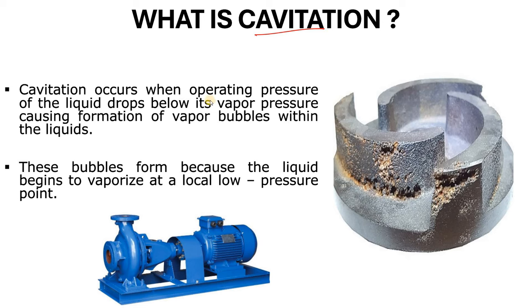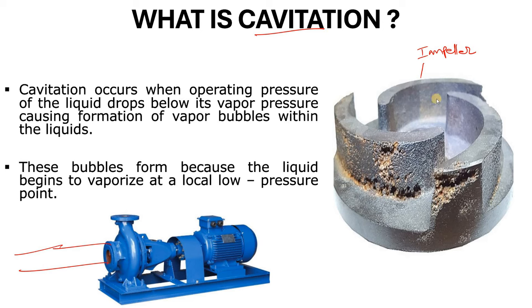So, what is cavitation? Cavitation occurs when the operating pressure of the liquid drops below its vapor pressure, causing the formation of vapor bubbles within the liquid. Let's suppose this is your centrifugal pump with an impeller. At the eye of the impeller, the pressure is very low because of the reduced area. As the fluid goes from the impeller to the casing and then to the discharge side, the area increases, and the pressure increases. The rotating impeller helps convert the energy.